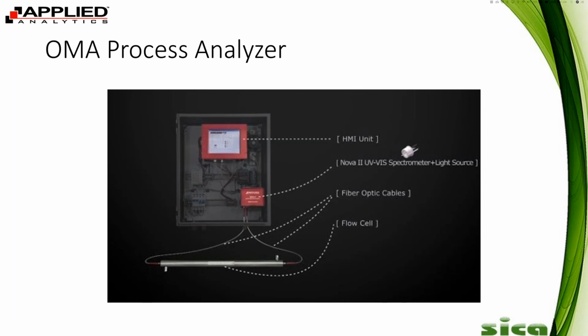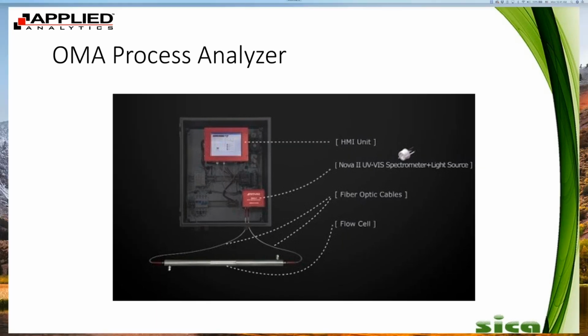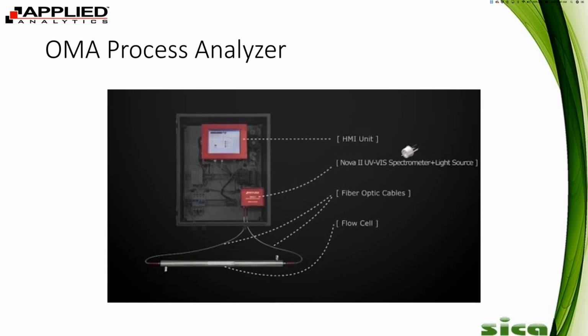You can't quite see it here, but you can add a heater with a PID, you can add coolers, you can add things like that. So you can install the analyzer really anywhere. You can install it in very hot or cold environments. There's customizable materials. All that's never really an issue. Hazardous areas should never be an issue for us. We have ATEX, IECEx, UL, Zone 1, Zone 2, you name it, it should be fine. So that's a little bit about our OMA process analyzer.